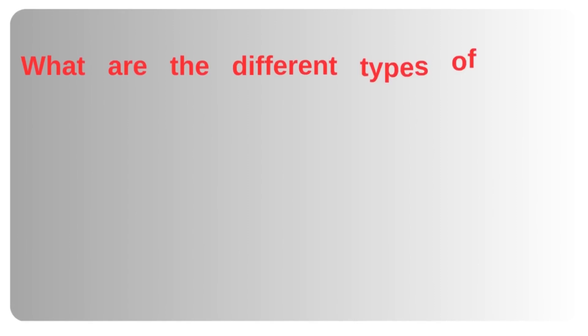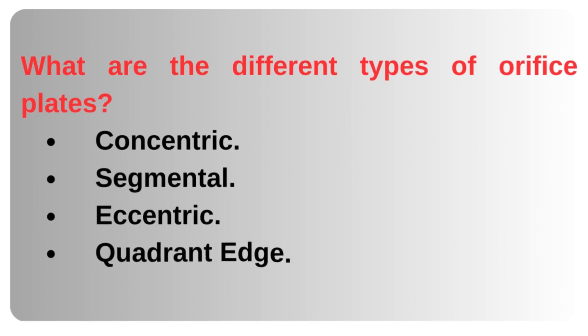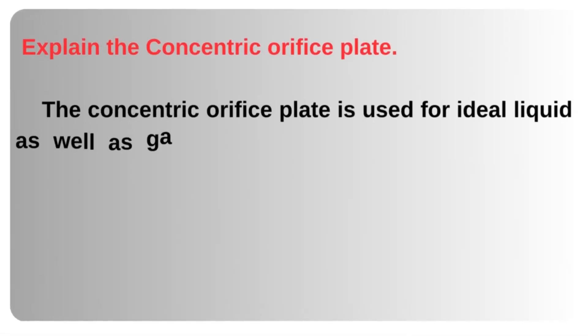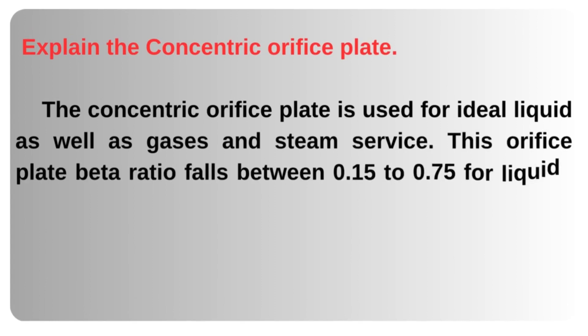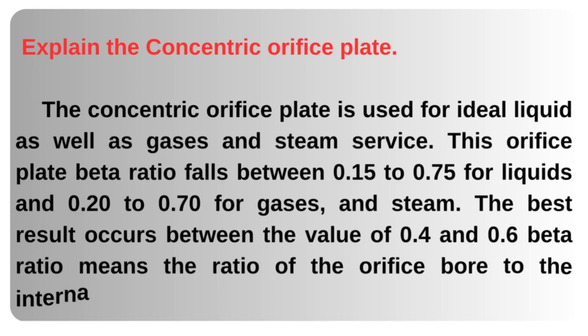What are the different types of orifice plates? Concentric, segmental, eccentric, quadrant edge. The concentric orifice plate is used for ideal liquids as well as gases and steam service. Its beta ratio falls between 0.15 to 0.75 for liquids and 0.20 to 0.70 for gases and steam. The best result occurs between 0.4 and 0.6 beta ratio.